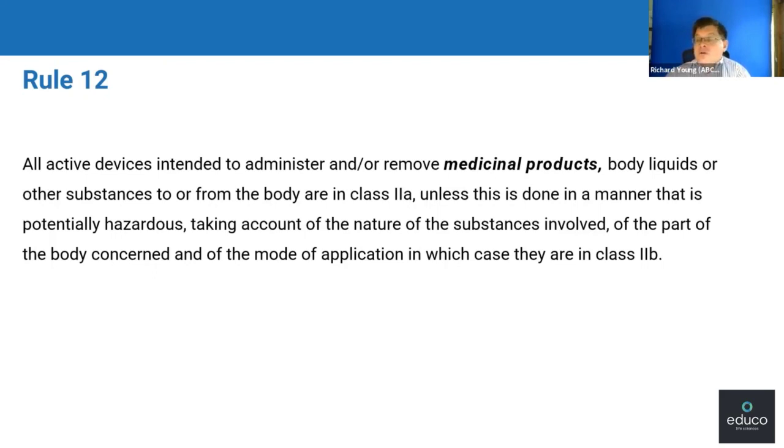So as you read through, multiple classification rules could apply to products. What you've got to do as you go through here is take the conservative approach. Take the highest risk classification applied to your product. It is always better for your notified body to be telling you you've overclassified a product than underclassified, because that can lead you to some problems going forwards.